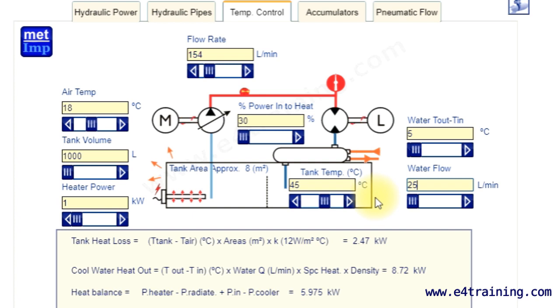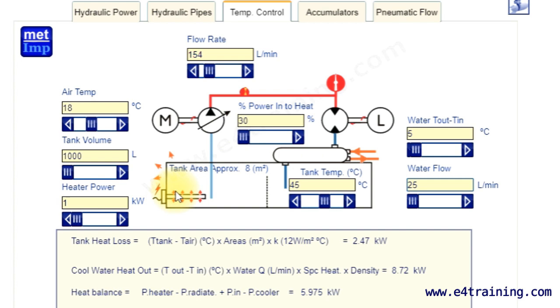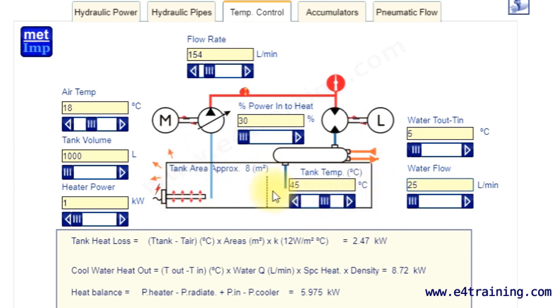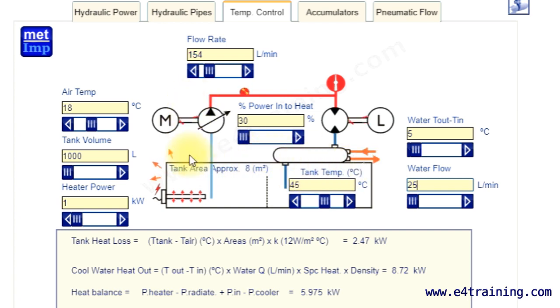Clearly if you put too much power in your circuit into a small reservoir, then it will overheat. But if you build a larger reservoir with lots of surface area, then it might lose too much heat and get too cold. We're trying to keep our reservoirs in a nice working temperature, 40 to 50 degrees C, so that the hydraulics is working nice and reliably and we don't damage our fluid.